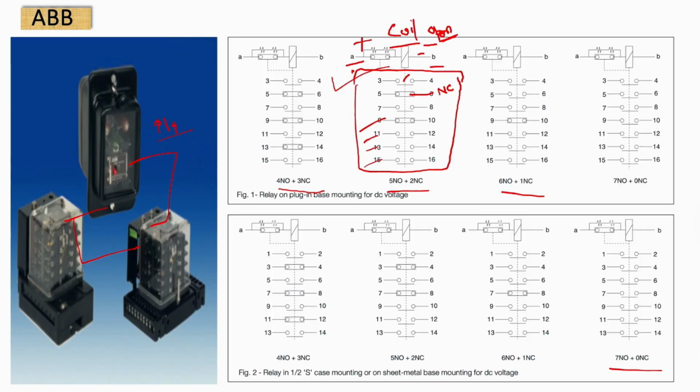As soon as my positive comes, from where will it come? It will come from the differential relay, the Buchholz relay, or the overcurrent relay. So, as soon as the positive arrives, the negative we already have to supply from the panel. Okay, so, the negative is already from the panel. If the positive comes from any relay, then the contacts here will change.